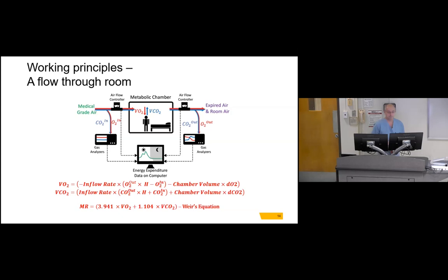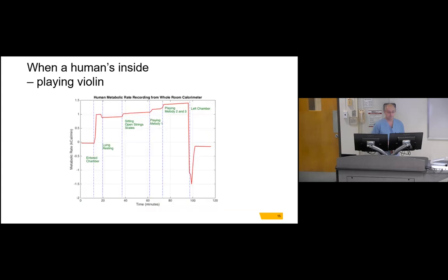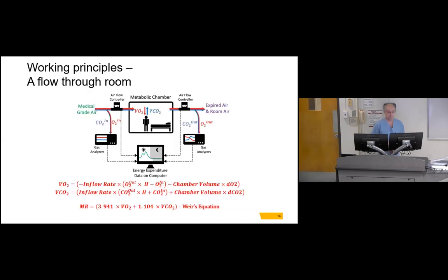So how does this work in our chamber? We first send fresh air into the chamber, and in our case, it's medical grade air supplied by the hospital. And we analyze the oxygen and the carbon dioxide concentration in the fresh air before the air goes in. And in the chamber, the subject will consume some oxygen and produce some carbon dioxide. So the gas concentration in the chamber will be different from the gas concentration of the air before it goes in.